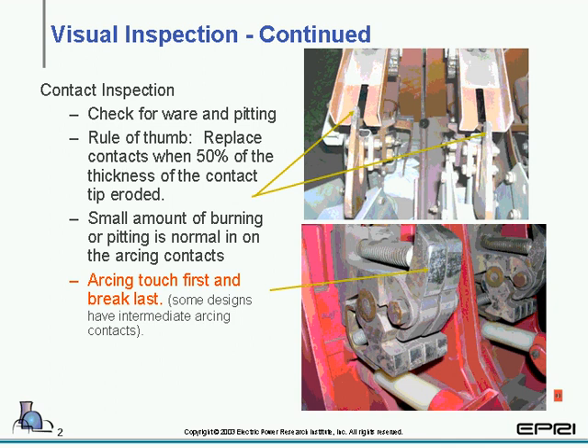Now, taking a deeper look at the contacts themselves, you're going to want to be checking for wear. As a rule of thumb, you want to replace contacts with 50% thickness of contact tip erosion. That can be shown with the yellow V'd arrows in the upper slide. You'll see that the one on the left is slightly longer than the one on the right, and that's caused by the erosion.